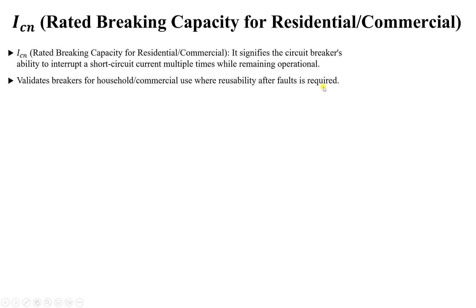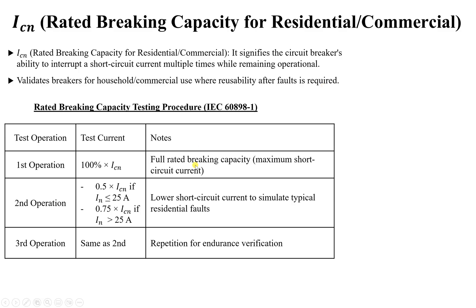ICN is used for household and commercial applications where reusability after faults is required. For example, if a short circuit happens in my house, I need my circuit breaker to be operable again afterwards. The testing standard for this is IEC 60898-1, which covers household and commercial applications. If ICN is 40 kilo-ampere, the testing proceeds as follows.